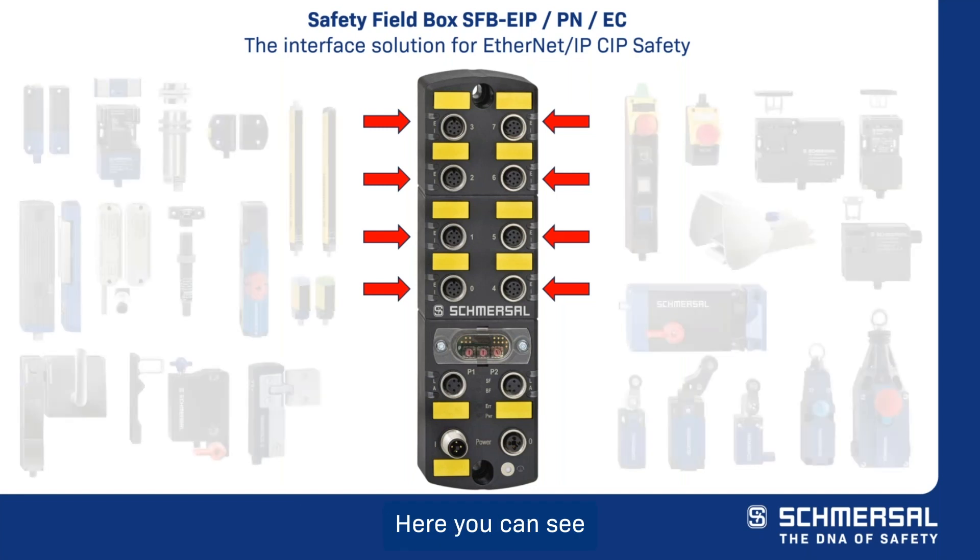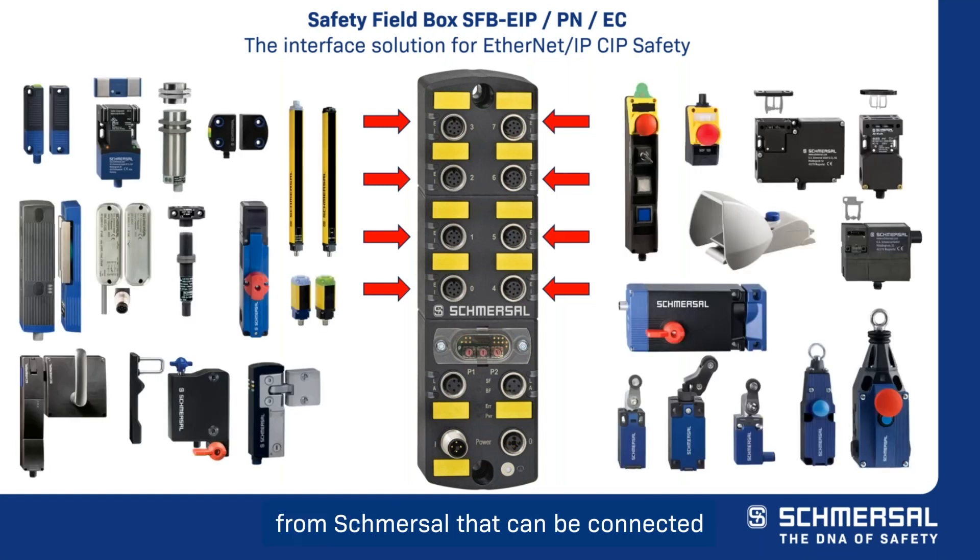Here you can see many of the safety devices from Schmersal that can be connected to these ports. Process transparency is optimized through the transfer of all diagnostic signals from the connected devices to the connected safety integrated PLC. Every device port is equipped with an auto-resettable fuse of 1.5 amps for line protection.